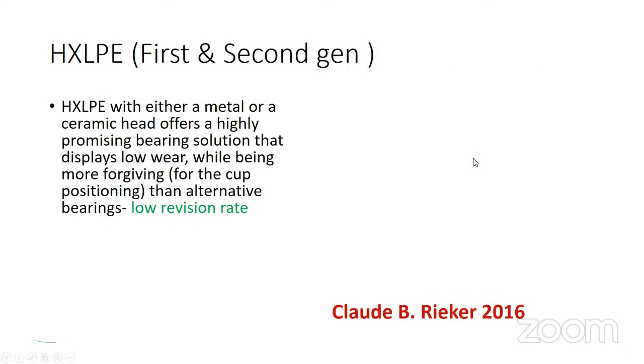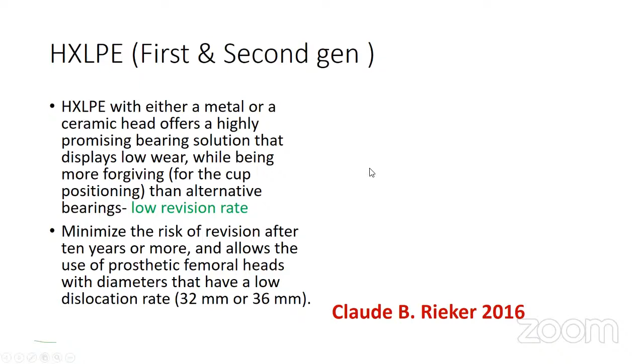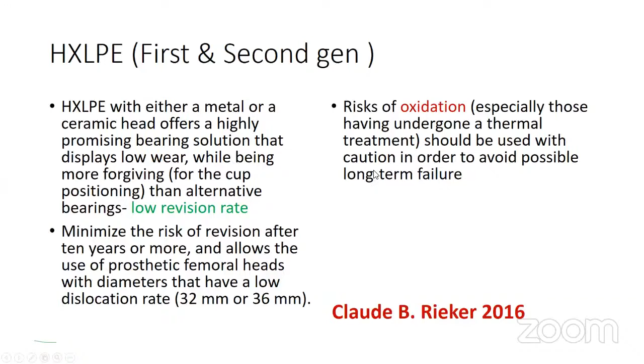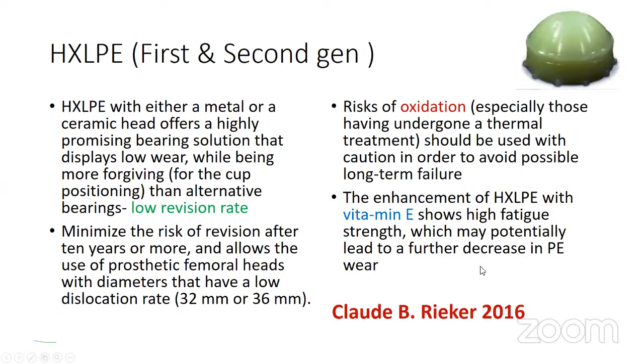Now it is asked, what is highly cross-linked polyethylene, and what are its advantages? So highly cross-linked polyethylene, with either a metal or a ceramic head, offers a highly promising bearing solution that displays low wear while being more forgiving for the cup positioning than alternative bearings. It has a low revision rate. It minimizes the risk of revision after 10 years or more. But there is a problem: there is a risk of oxidation. That is why it is combined with vitamin E. Vitamin E is added for reduction of oxidation. And this is now very popular.